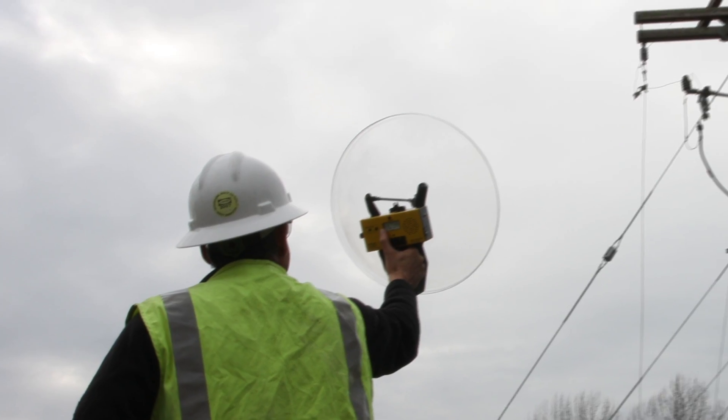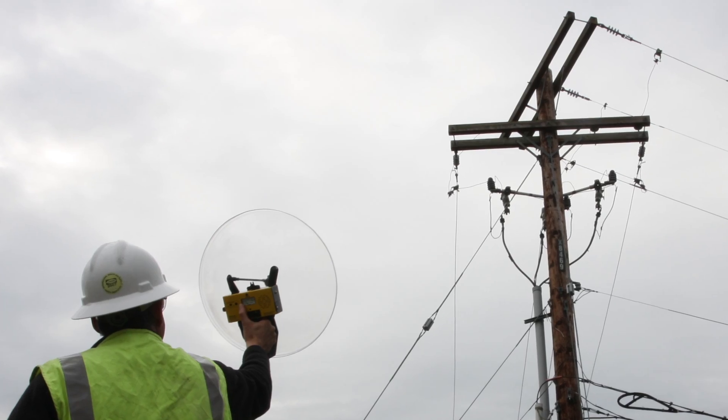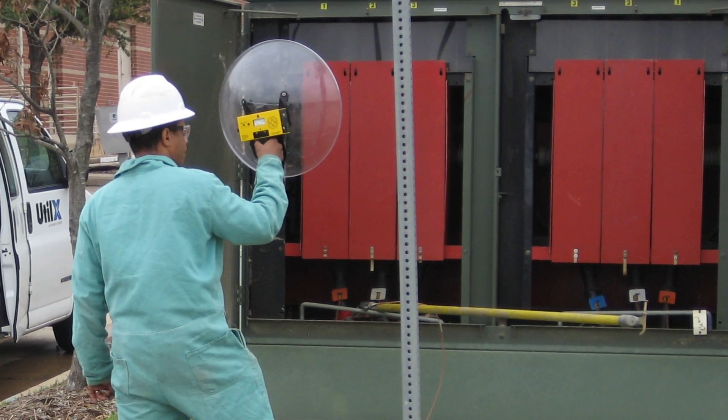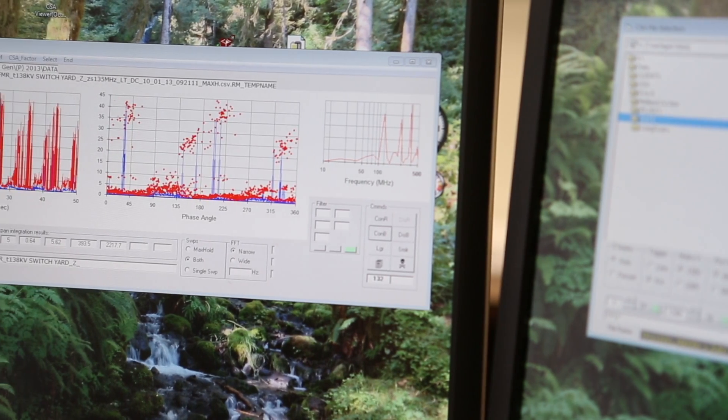The technician surveys the surrounding of each test point location and the adjacent circuits for sources of noise using an assortment of state-of-the-art radio frequency, ultrasound, and infrared tools.